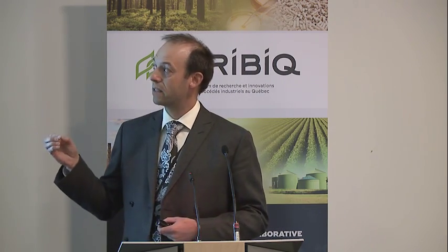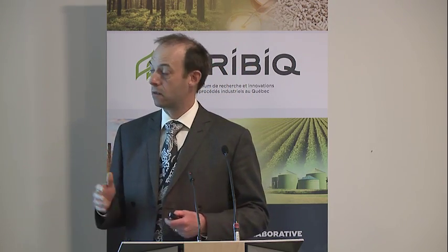Now, when it's installed, you want to start it up. So it is required to have some operation qualification. The operation qualification is there to demonstrate that the equipment does what it's supposed to: about the quality, the rate, the yield. This OQ is done on the site. At this moment, OQ is done mainly by the company, the owner of the equipment, and the engineers can assist them to prepare the documentation, to assist in the qualification, and to prepare the tests also.